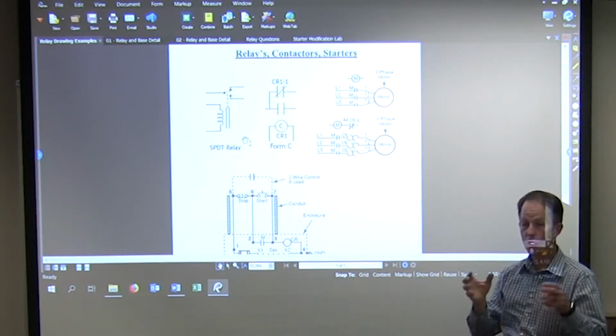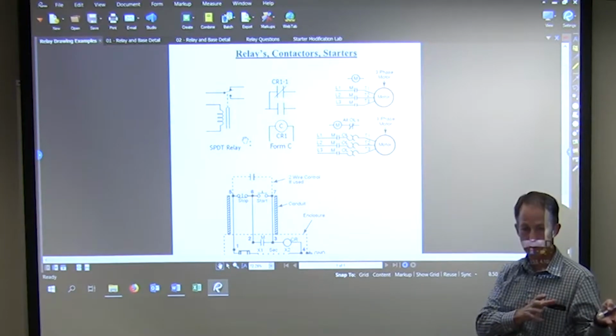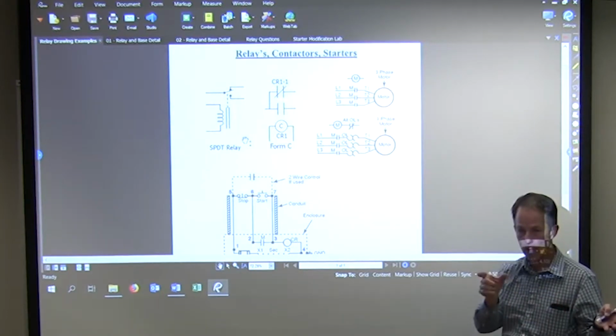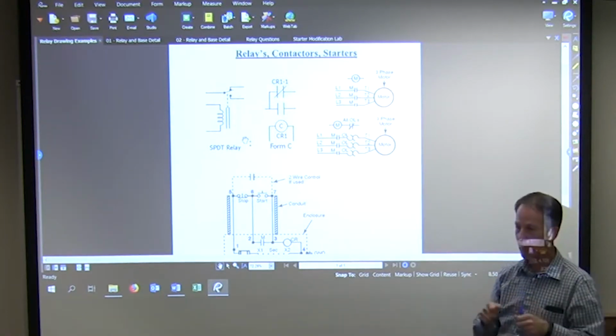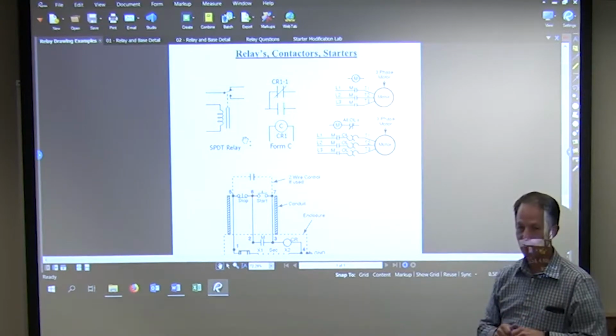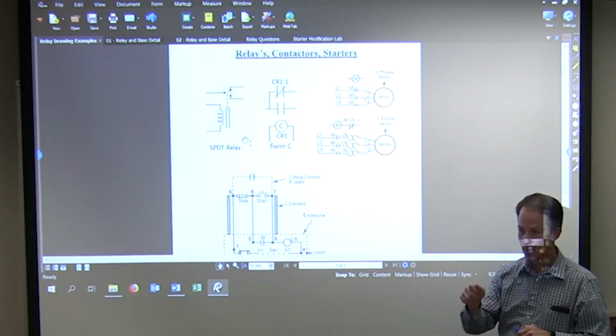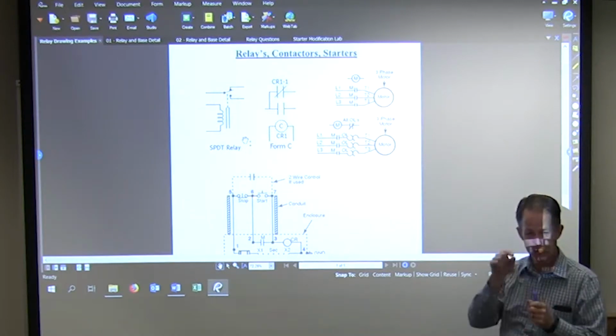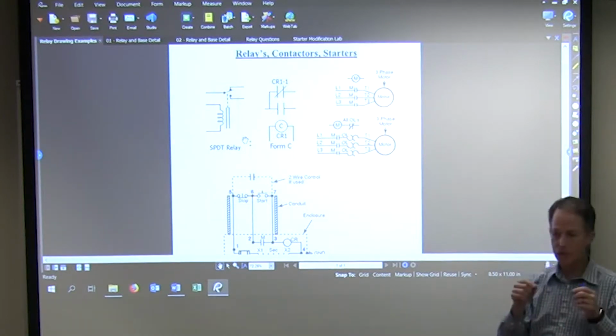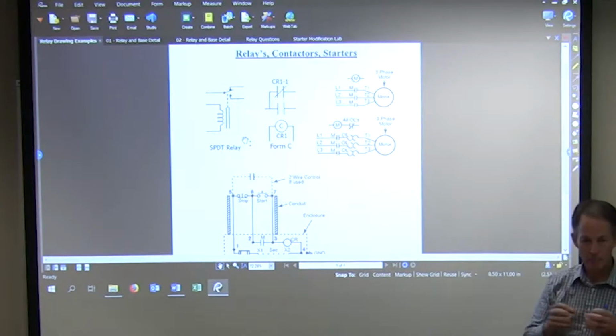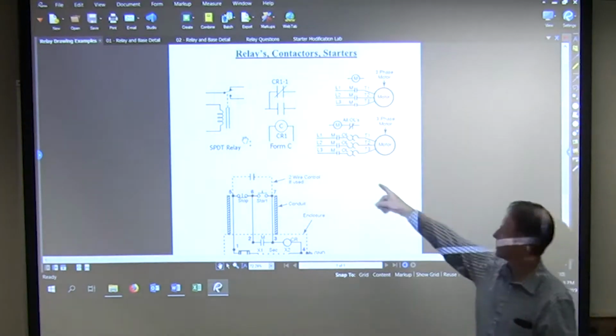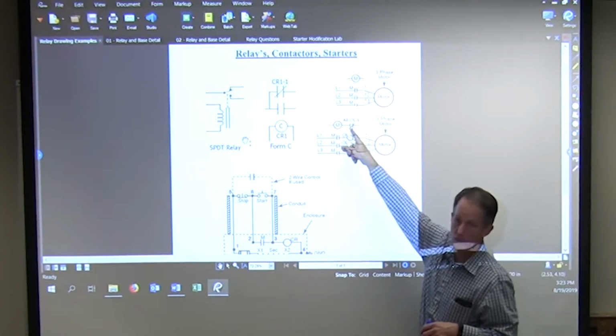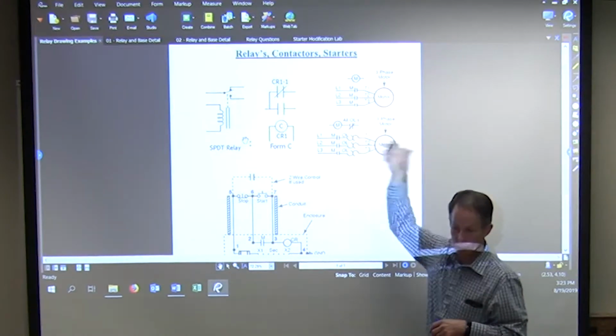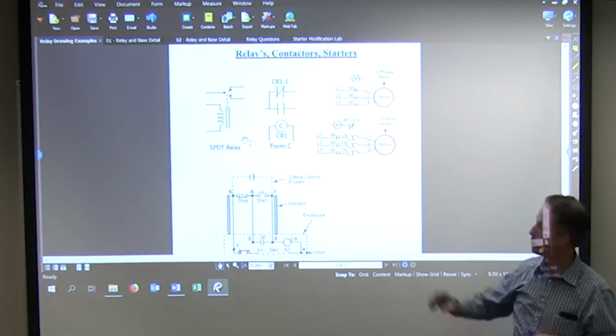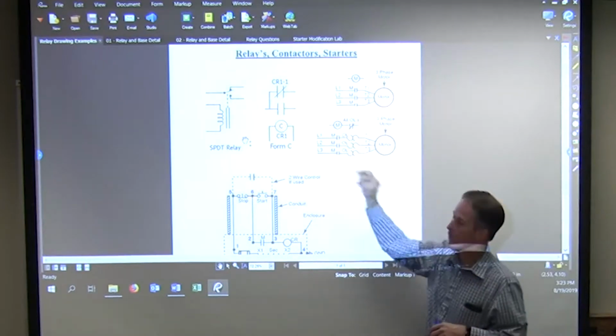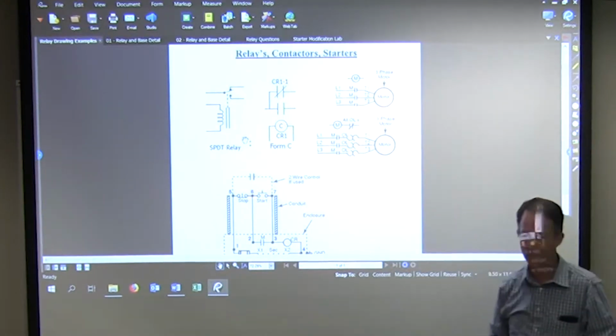Okay, so in the old days we had what we called heaters, right? It was a kind of metal, little clip-in pop-in thing. We've still got plenty of them around, and solder pots too. The little solder pot basically gets to the melting point determined for that size, it melts through and breaks the overload, which opens it up, right? And it basically takes out the ability for the motor to turn. We shut all three of those contacts down at the same time.